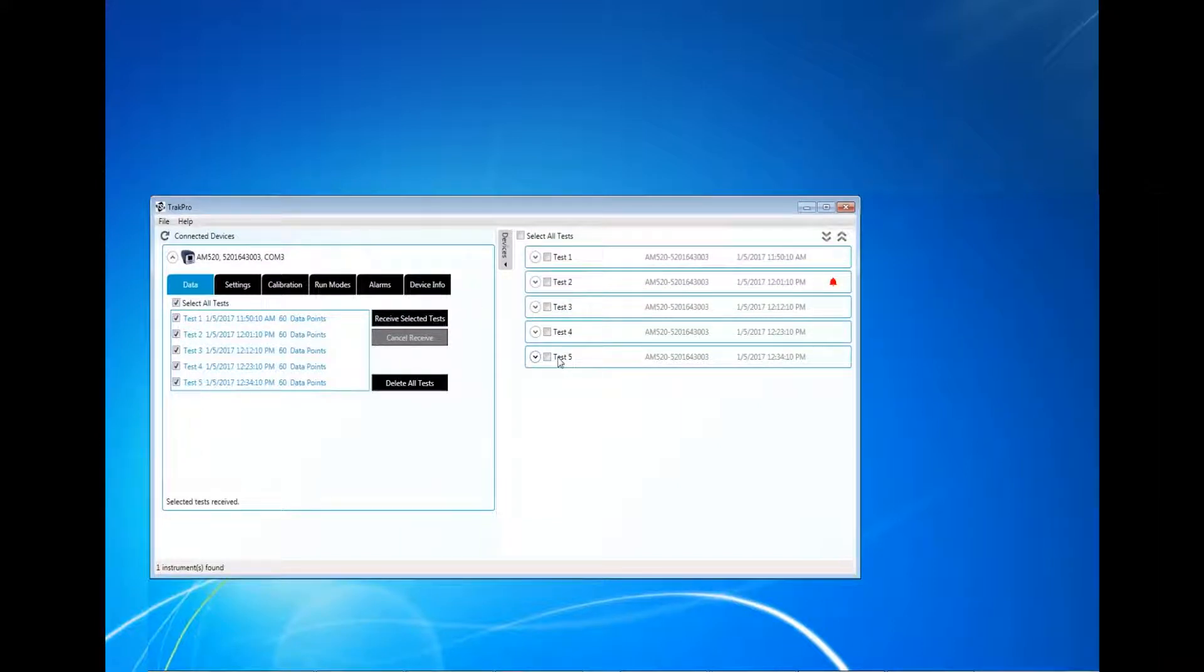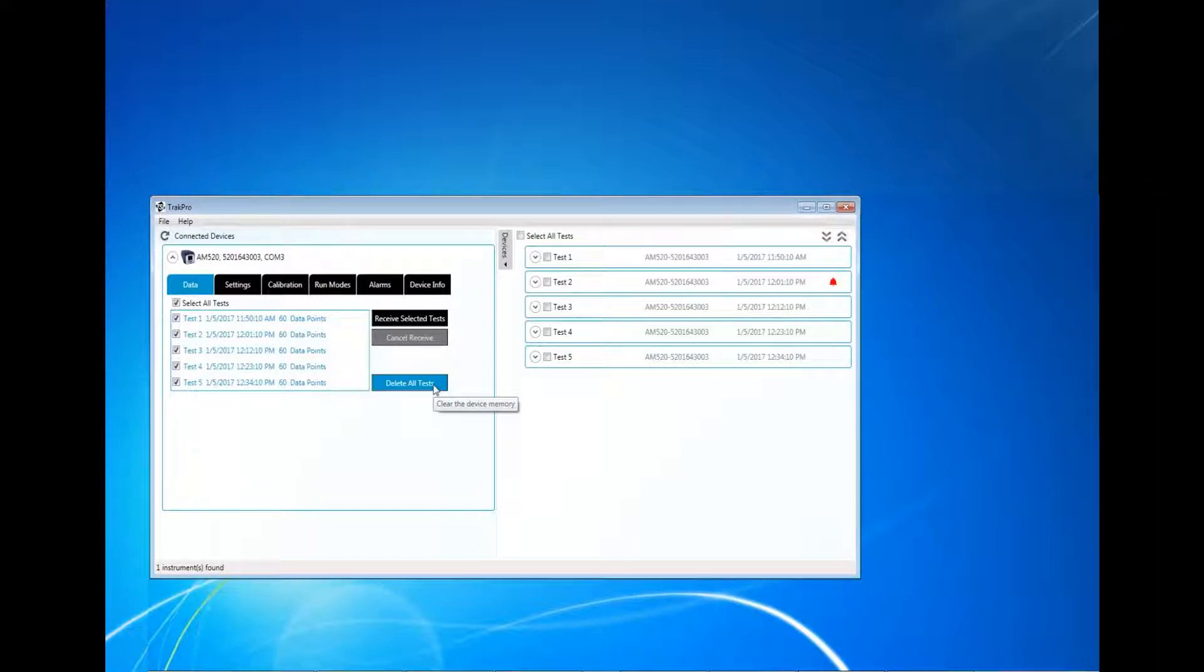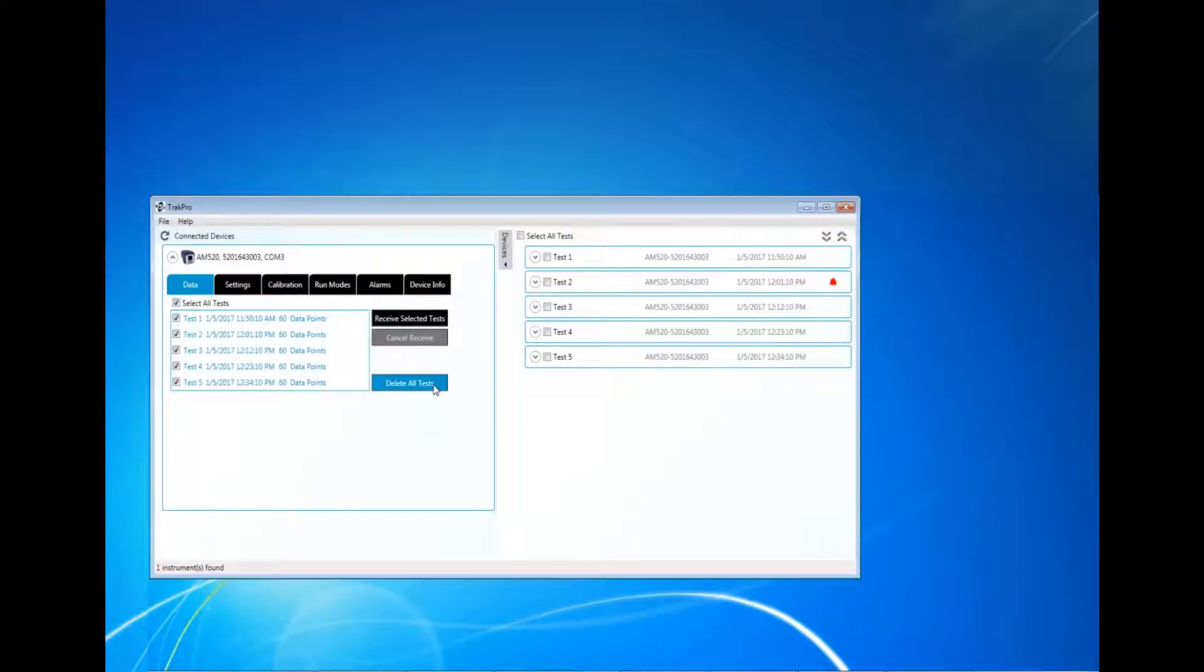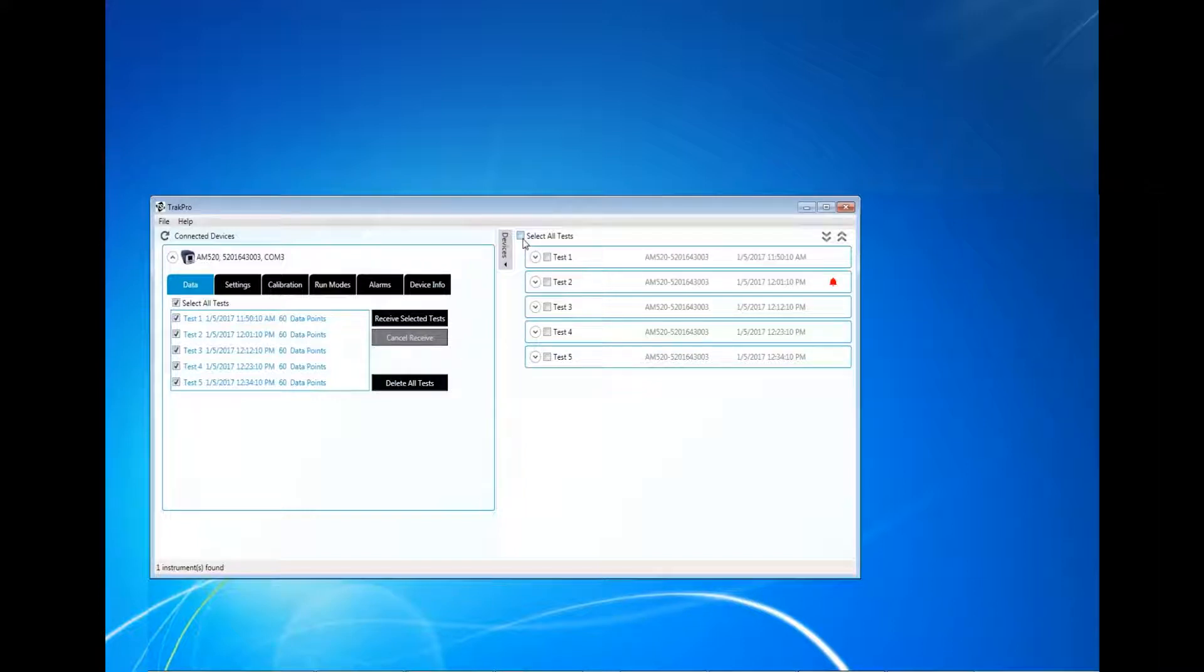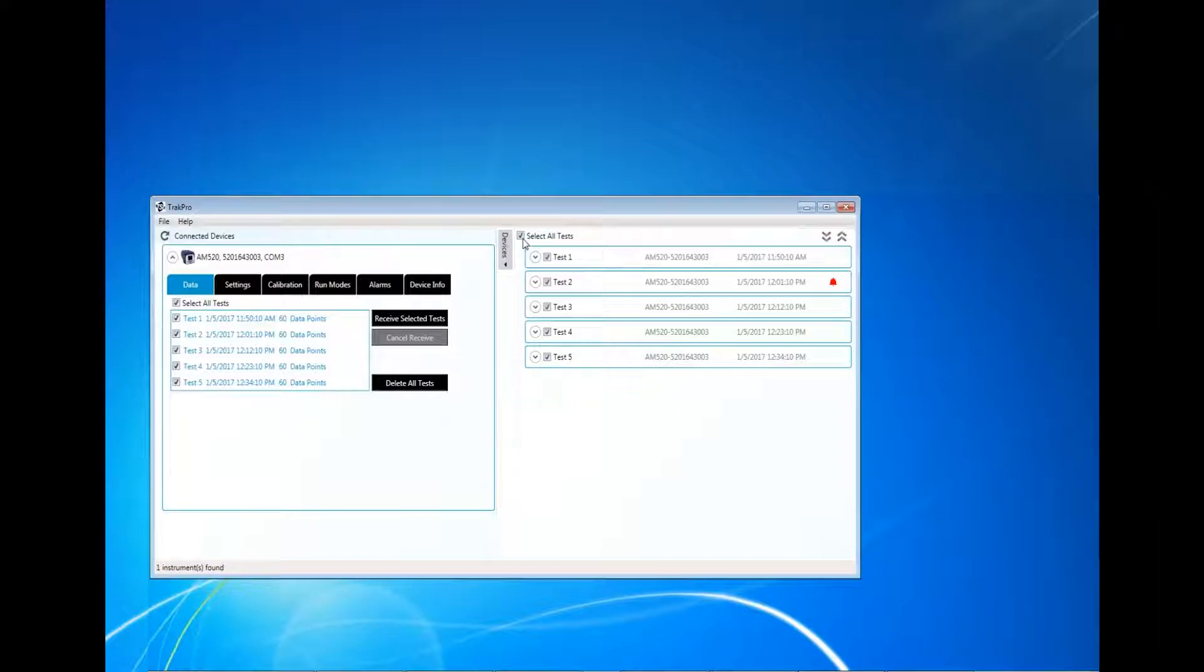Delete All Tests allows the user to delete all the log data files from the instrument's internal memory directly from TrakPro. This can also be done at a later time using the AM520 menu system. At this time, the test data can be saved in the form of TrakPro files.